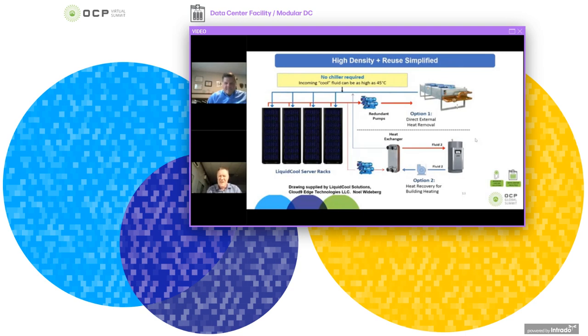This means the cost of cooling is minimized. More importantly, these temperatures are actually getting to the point where they're starting to become useful for heat recovery. So once you start going from 45 degrees up to 60 degrees, you're in the range where you've got underfloor heating and building comfort heating. This allows the reuse to be a lot easier out of this high density solution.